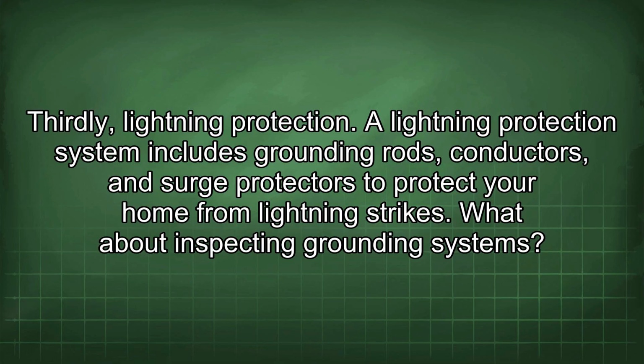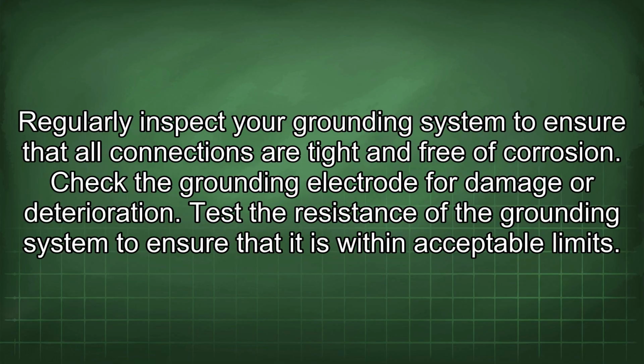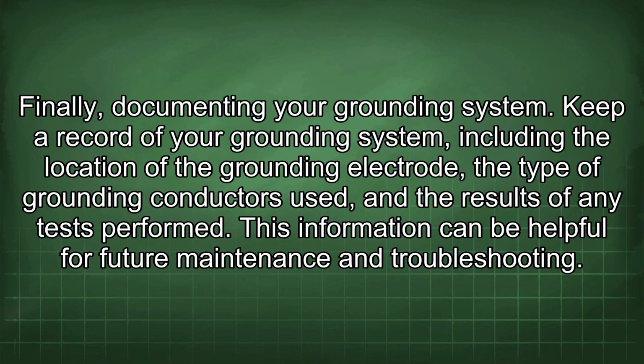What about inspecting grounding systems? Regularly inspect your grounding system to ensure that all connections are tight and free of corrosion. Check the grounding electrode for damage or deterioration. Test the resistance of the grounding system to ensure that it is within acceptable limits. Finally, documenting your grounding system. Keep a record of your grounding system, including the location of the grounding electrode, the type of grounding conductors used, and the results of any tests performed. This information can be helpful for future maintenance and troubleshooting.